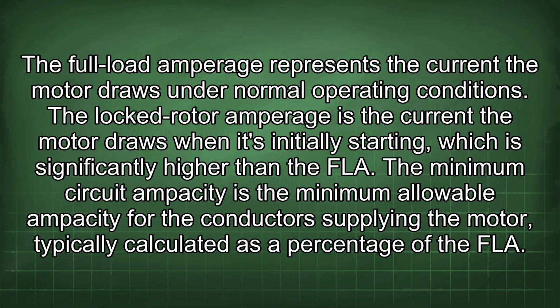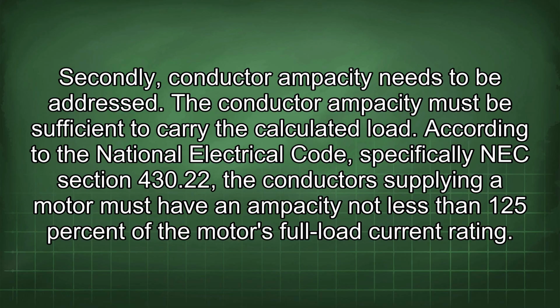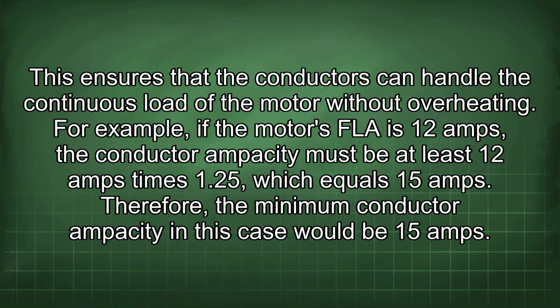percentage of the FLA. Secondly, conductor ampacity needs to be addressed. The conductor ampacity must be sufficient to carry the calculated load. According to the National Electrical Code, specifically in NEC section 430.22, the conductors supplying a motor must have an ampacity not less than 125% of the motor's full load current rating. This ensures that the conductors can handle the continuous load of the motor without overheating. For example, if the motor's FLA is 12 amps, the conductor ampacity must be at least 12 amps times 1.25, which equals 15 amps. Therefore, the minimum conductor ampacity in this case would be 15 amps.